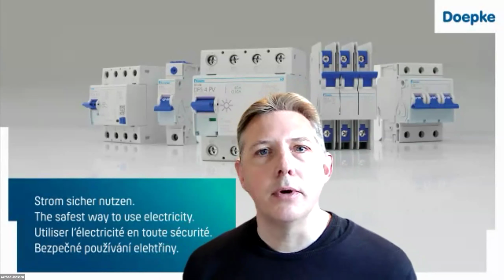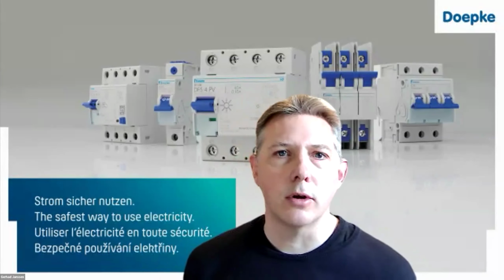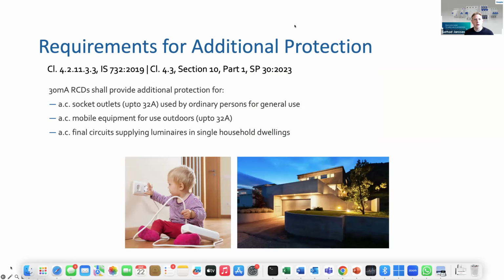Yes, this is quite wrong or dangerous. So 30 milliamp is required for human protection. If there are sockets or whatever where human protection is needed, 30 milliamp RCDs have to be installed. If it goes higher and you do not have the risk for a human to touch a live wire, if it's only about fire risk, for example, then 300 milliamp or 100 milliamp may be enough, but it depends on who is able to touch it or where the risk is. So 30 milliamp for human protection, 300 milliamp for fire protection. Thanks. I'll just show you the requirements in the Indian standard.